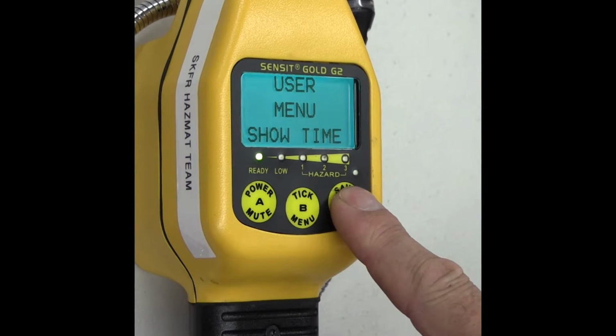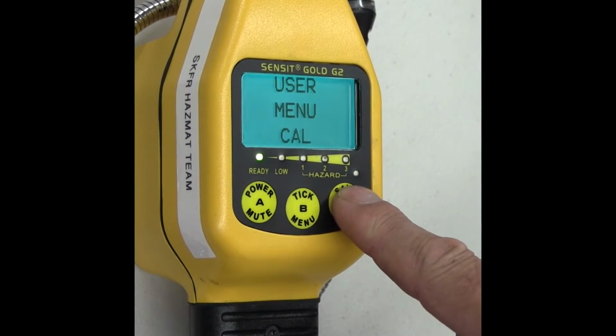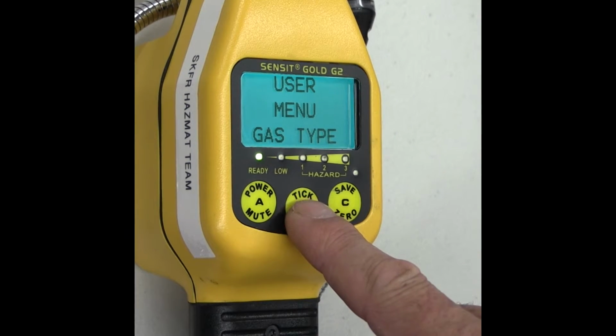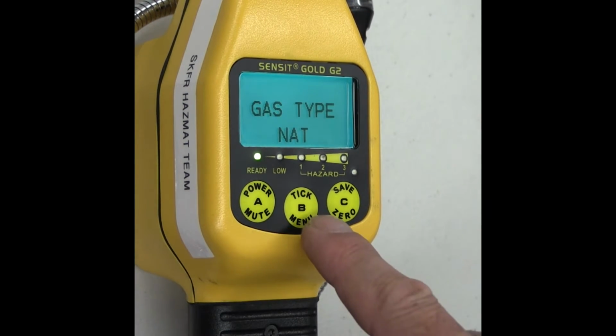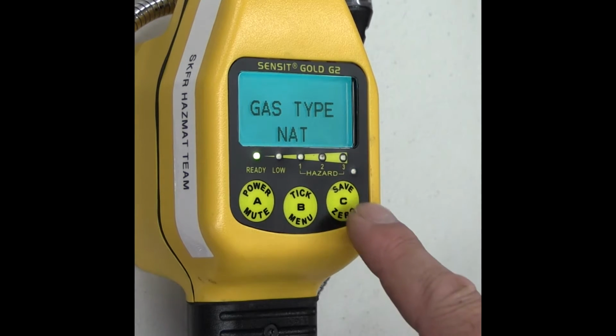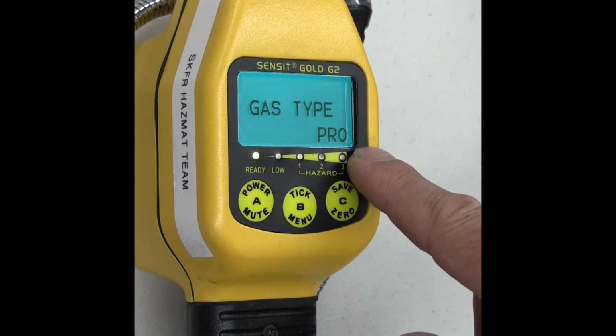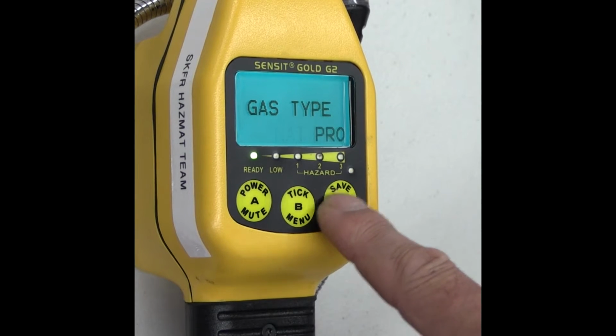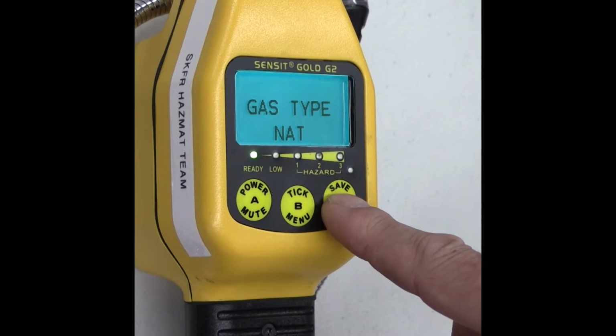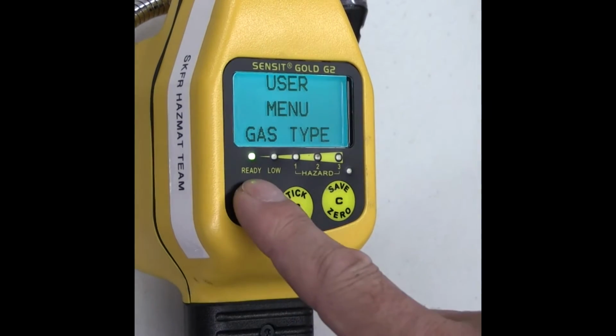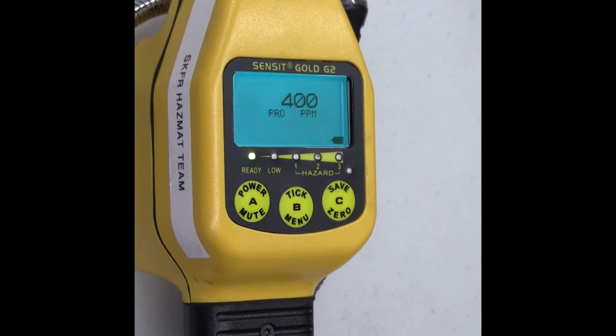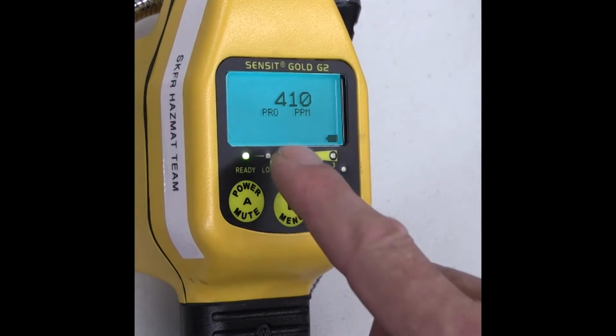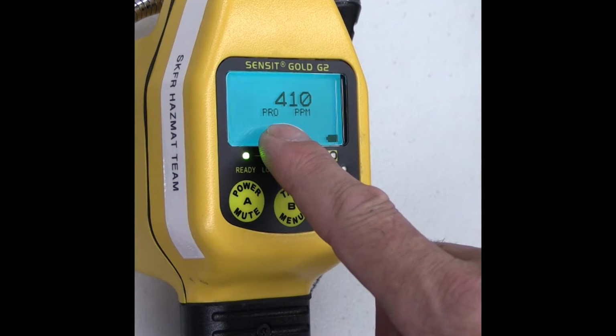Use the C button to walk through the menu until you get to gas type. Press the B button to select that, and at this point you'll see natural gas here, or if you press the C button you'll see propane here. You can use the two buttons to go between them. When you have the gas that you would like, press the A button twice to go back to the gas menu. Note the display will show the gas that you've selected. Now it's PRO for propane.